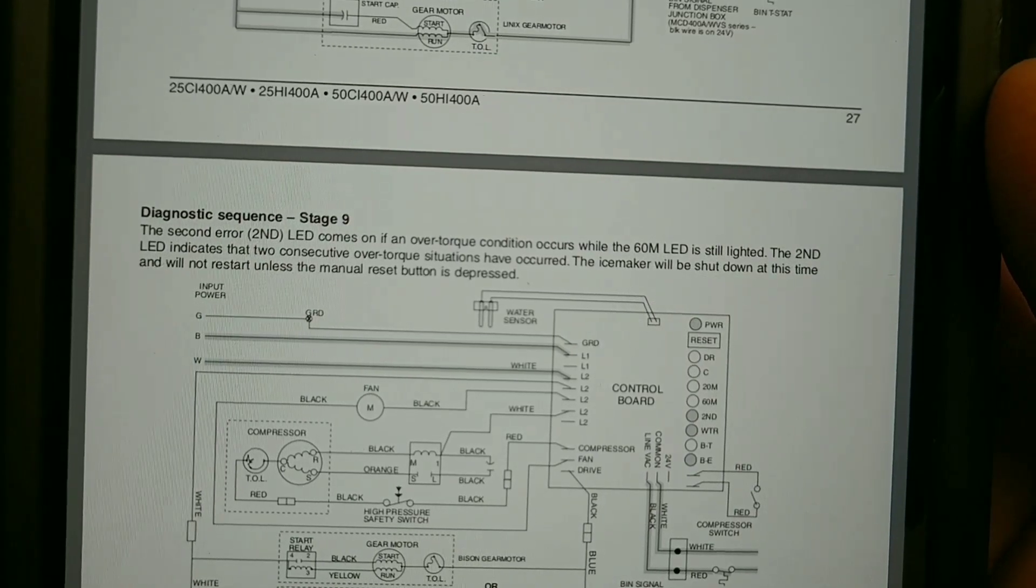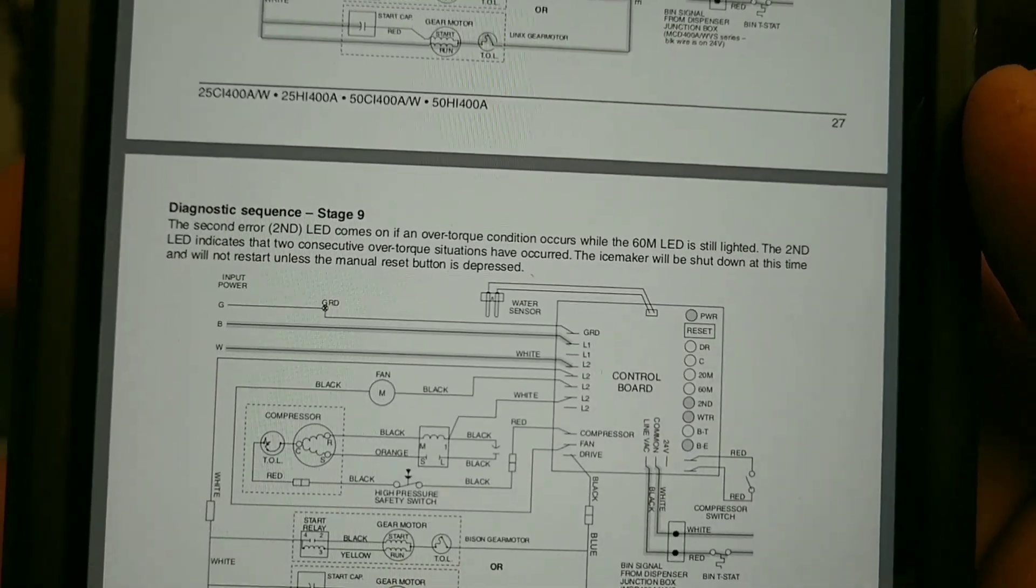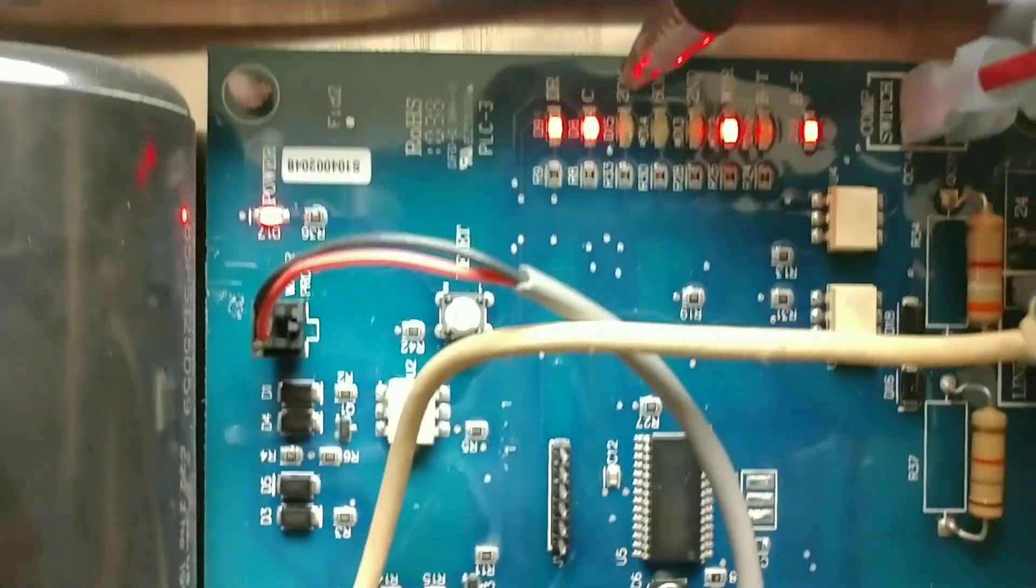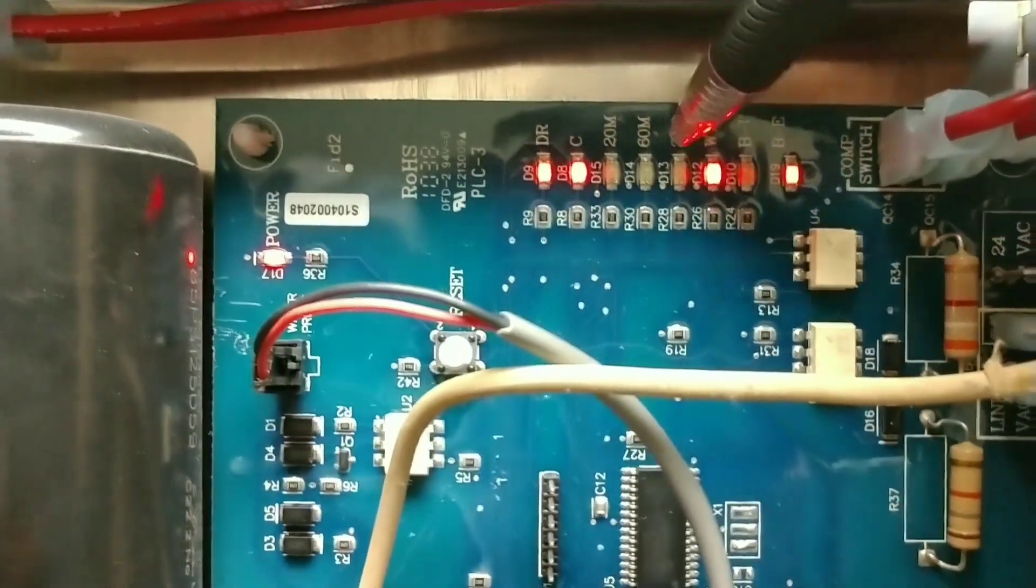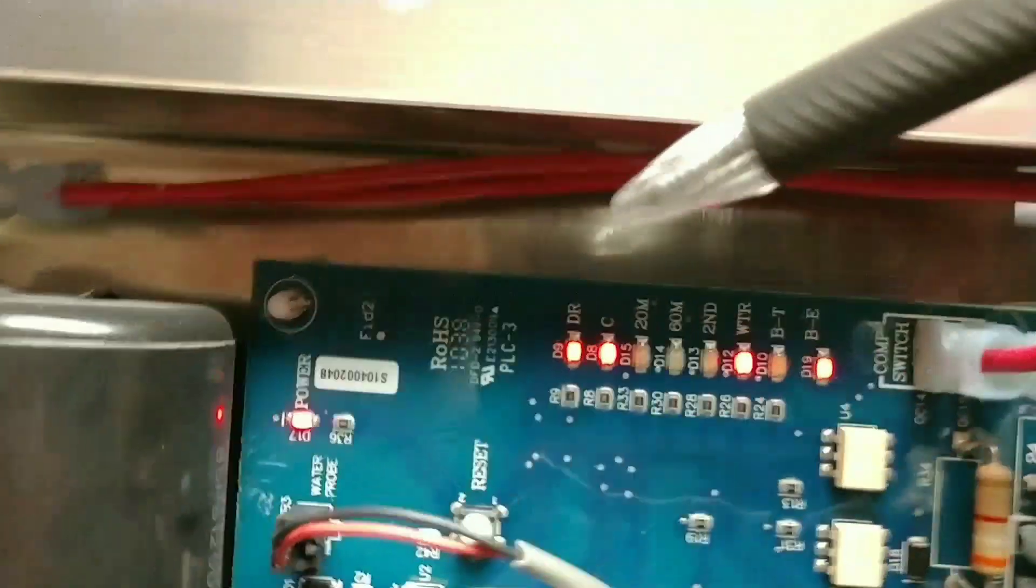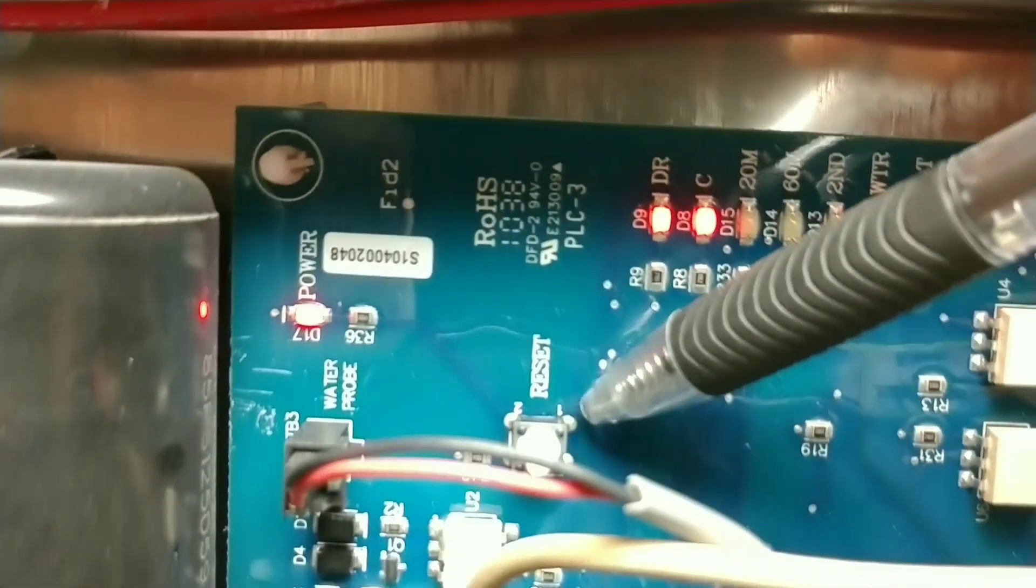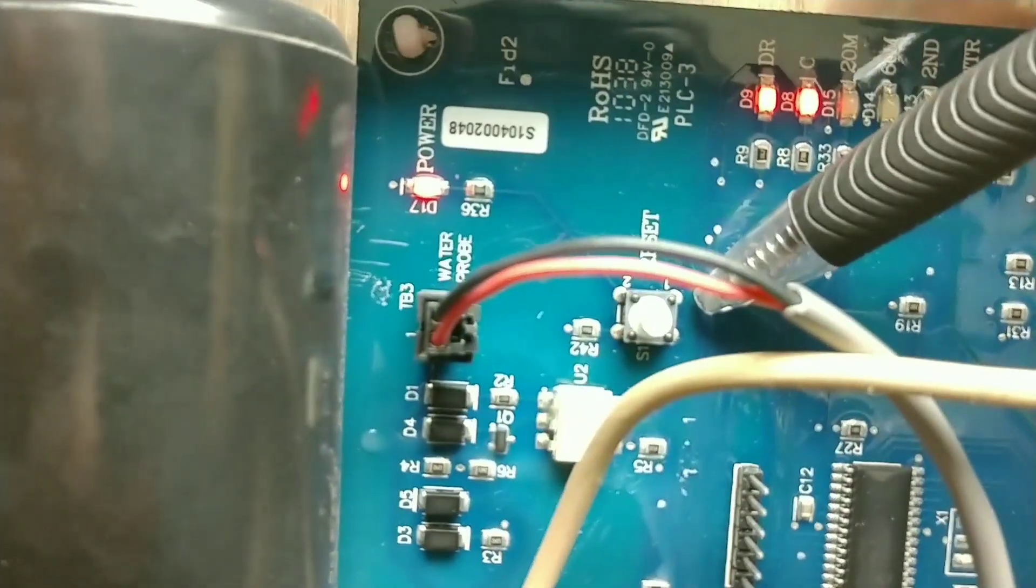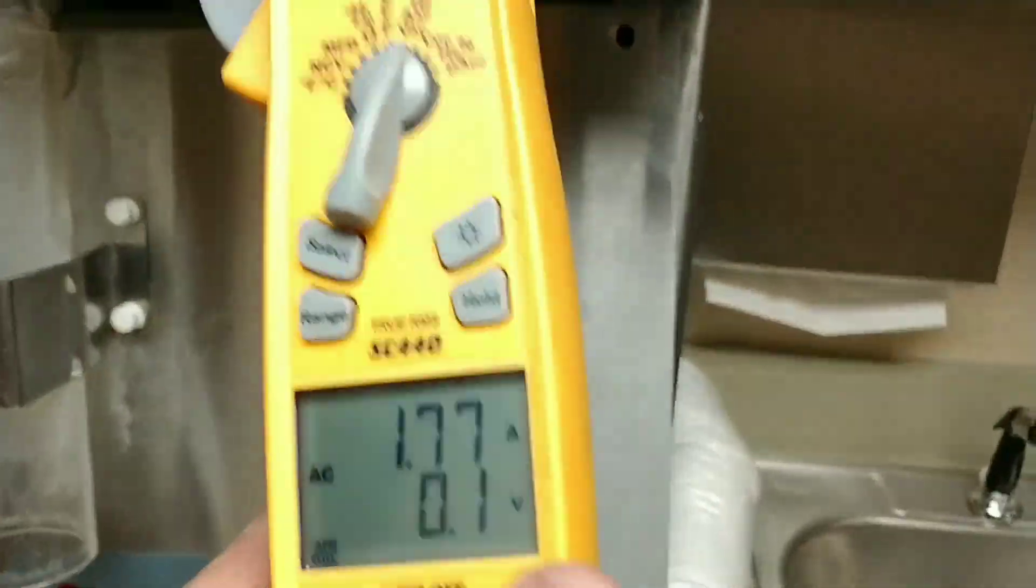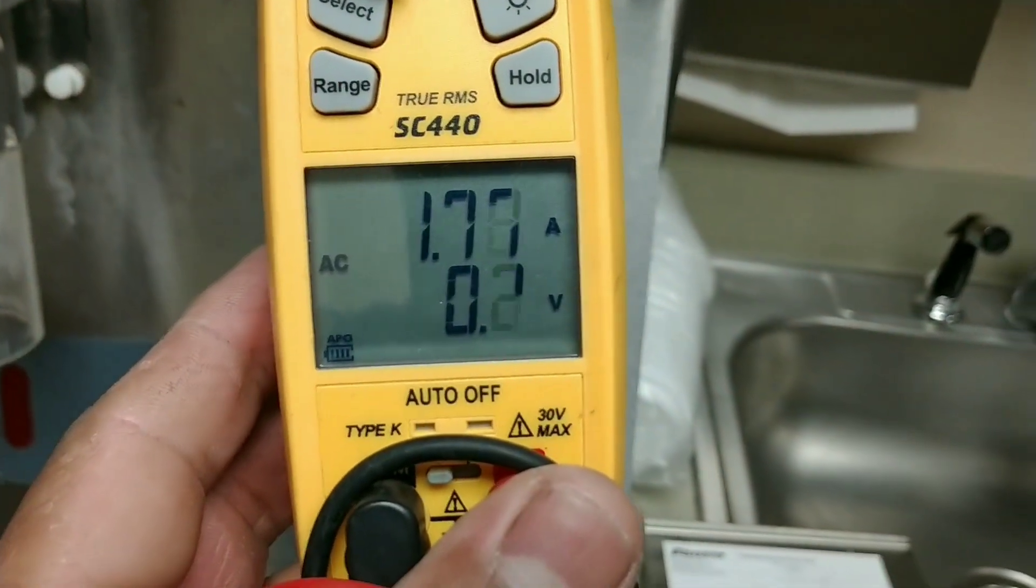So like I said, when I showed up we had the 20, the 60, and the second LED. All you gotta do on these Folletts is hit that reset right there, it's a nice little reset button, and you begin normal operation. As you can see we're running about 1.7 amps, that is actually slightly high.